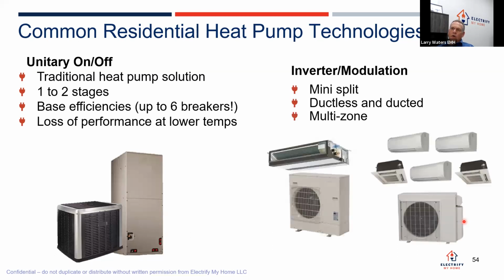Or we have inverter modulation systems. And these systems are a little bit different, where they're not on and off. These systems will run a little bit longer, and they use energy differently. They take power from the wall, they convert it from AC to DC, and then they back invert it internally to an AC 3-phase power. That AC 3-phase power has the ability to exist or run outside the normal 60 hertz electrical range. So it can ramp up, it can speed up.